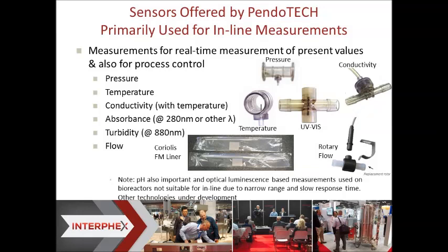This is a list of the primary measurements used for inline measurement. So the measurement also facilitates the ability for data collection and process control versus a simple mechanical type gauge. The main ones used by many people in the industry for filtration, chromatography, bioprocess. These are pressure, temperature, conductivity, along with the temperature measurement, absorbance, turbidity, and flow. And pH is obviously an important measurement. It's not mentioned here. Much of the single-use pH technology that's available is more suitable for a bioreactor versus downstream processing where things are happening very quickly, and the luminescent technology operates in a fairly narrow range with a slow response time. These graphics are pictures of our products: pressure, conductivity, UV-VIS, temperature, a Coriolis liner, and a rotary flow meter.